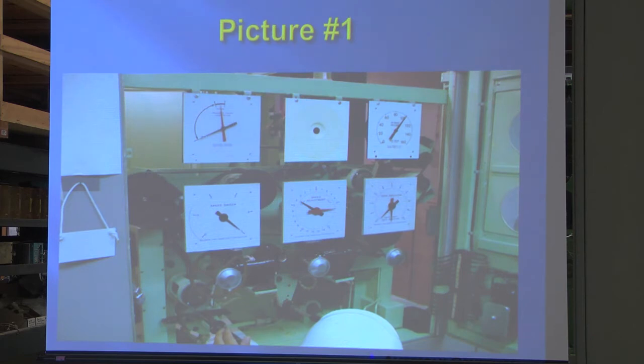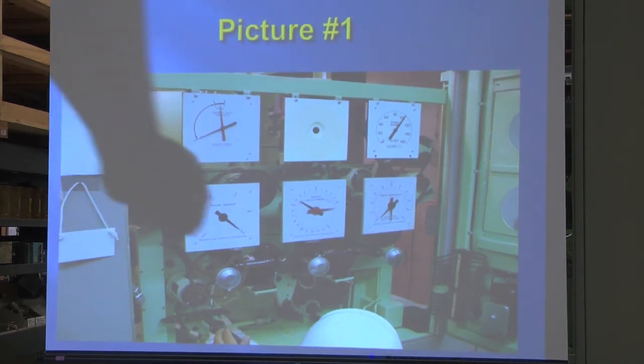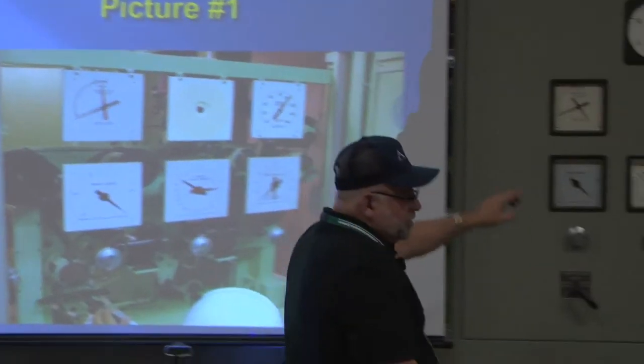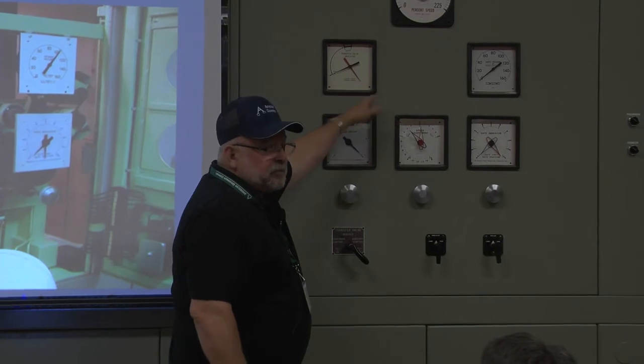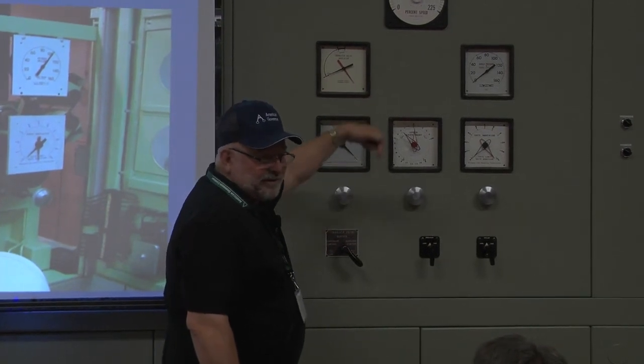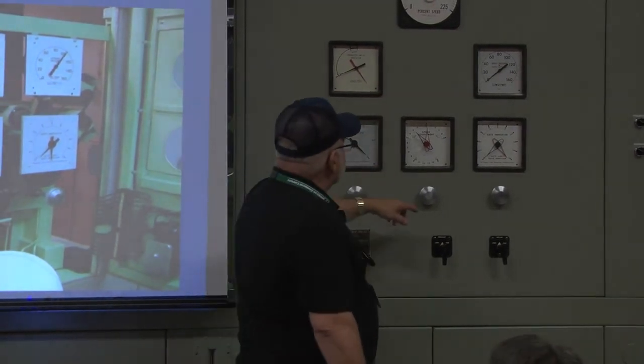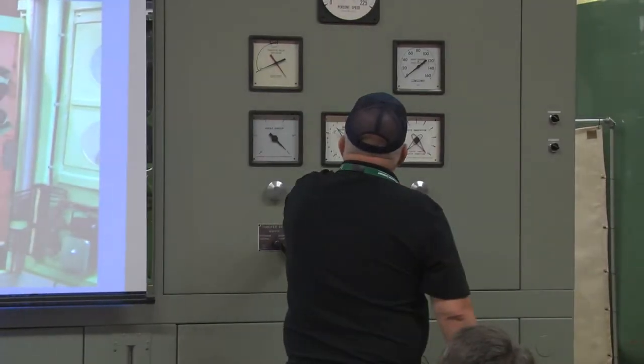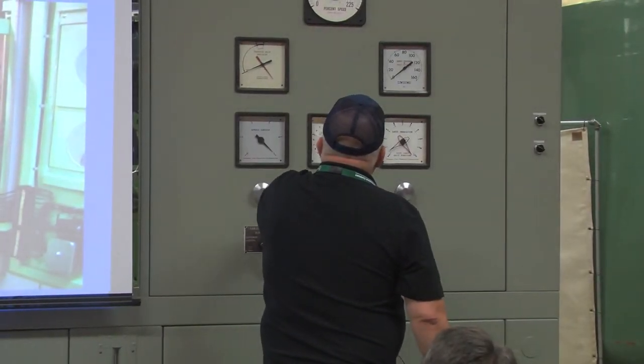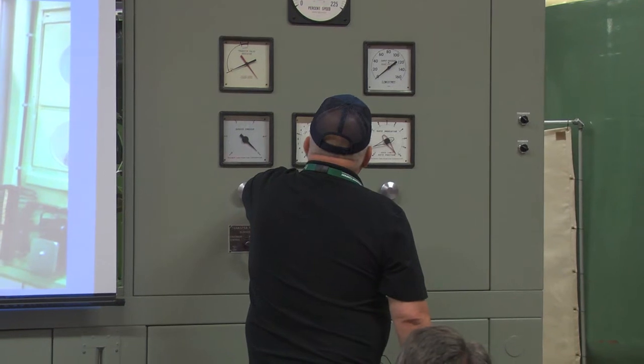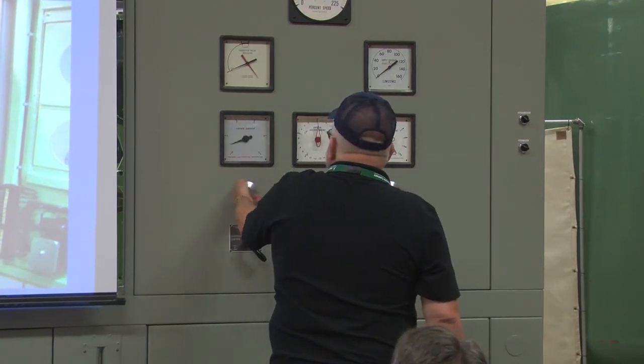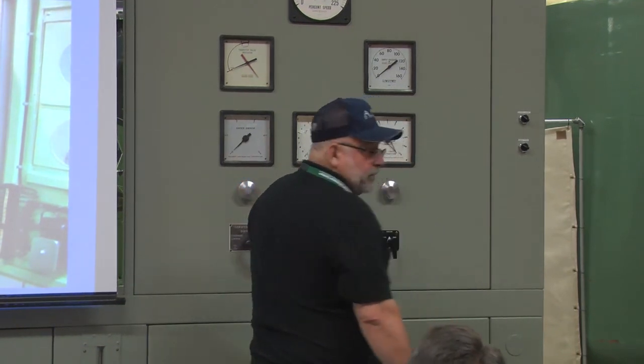Okay. Well, normally, like on a Woodward unit, if I was going to set the speed on a unit, you have to take the little locking nut out. This one doesn't have a locking nut on it, by the way. It's just the one down below. So if I was going to set this, I would bring this to 100%. I would move my droop to 0. I would have field on the unit, and I would set that speed.